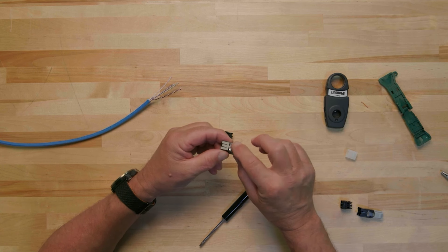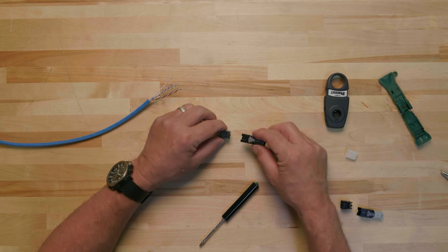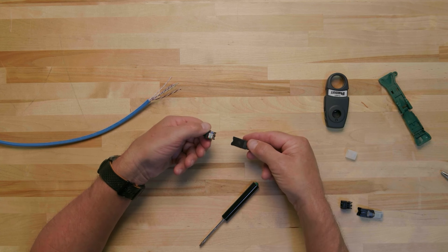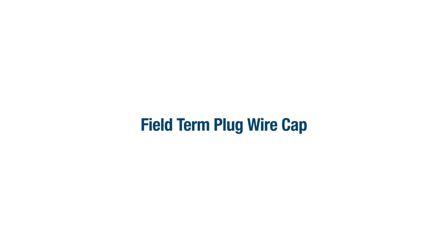To properly terminate any field term plug, the most important thing to consider is the orientation of the plug compared to the wire cap and color-coded conductor pairs. To help us understand proper orientation, let's start by identifying the parts of the wire cap and field term plug that we will be referencing. When terminating the field term plug, you must use the field term plug wire cap. It is not interchangeable with a Minicom TG wire cap because the field term plug wire cap is smaller.